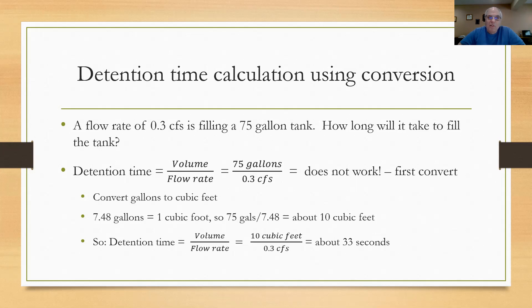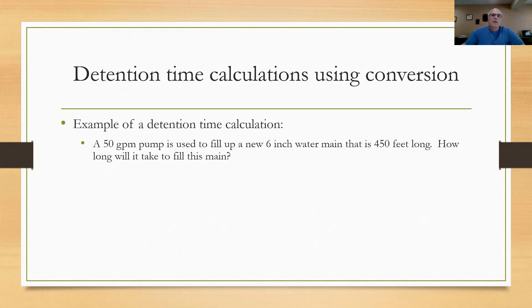I know that in one cubic foot, there's 7.48 gallons. So if I have 75 gallons divided by roughly 7.48, I'd come out to about 10 cubic feet. So now I can do my detention time problem because I have units that are the same. If I put the volume up on top in the numerator, that's the 10 cubic feet, and divide it by the flow rate of 0.3 cubic feet per second, I would see that it would take about 33 seconds to fill that tank up. Not very long.